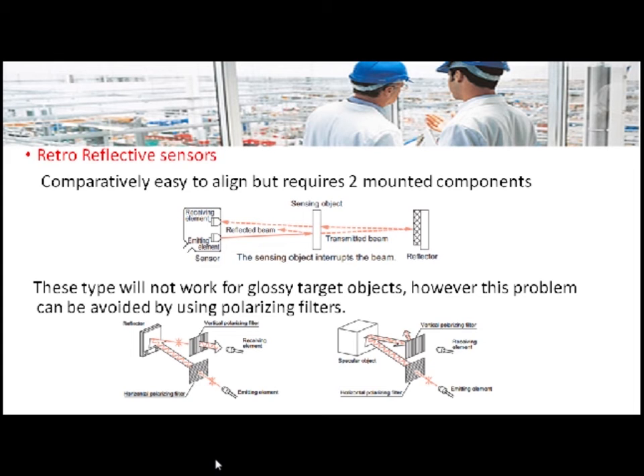This problem can be solved by using polarizing filters. The electromagnetic wave coming from the source is of a random nature and the light will be in all directions. By using a horizontal polarizing filter, it will allow the electromagnetic wave in only the horizontal plane, and similarly a vertical polarizing filter will allow it in only the vertical direction. The reflector converts the polarized signal into an unpolarized signal, which is then detected by the receiving element. However, if a glossy or specular object is present, it will not convert the polarized signal into an unpolarized signal; instead it reflects the same horizontal signal toward the vertical polarizing filter where it is blocked and not detected by the receiving element.